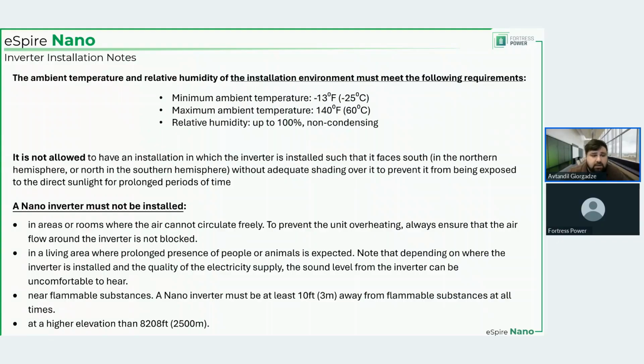Now, again, this could be subject to change. Maybe we're going to come up with a derating table, so for every 100 meters, you derate the system by so much, and that will help. But again, that elevation limitation is due to the fact that this is an air-cooled unit. The higher the elevation, the lower the air density, so the lower the cooling efficiency. Right now, this is the limit, the value I mentioned a moment ago. But in the future, we could come up with a derating plan and deploy that. But for now, please adhere to this limit.